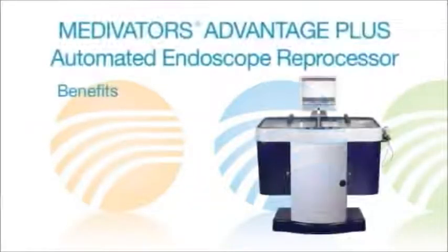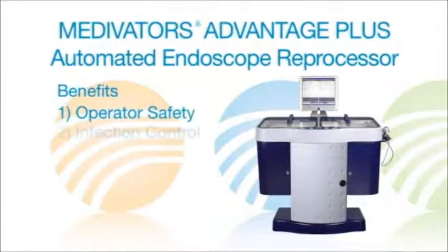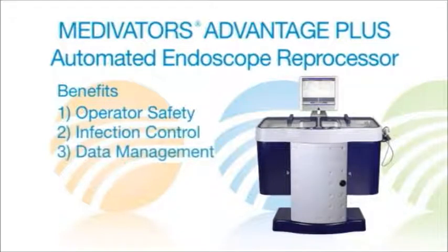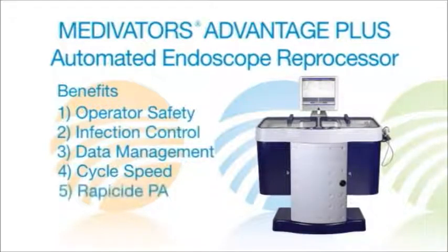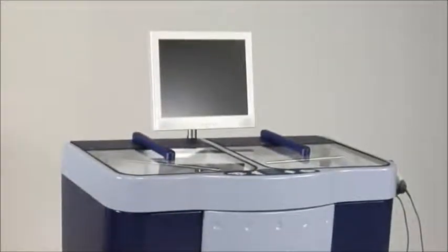The Advantage Plus was designed to meet customer needs with five major benefits: operator safety, infection control, data management, cycle speed, and the use of an environmentally friendly high-level disinfectant called Rapicide PA. These units provide a validated method for reprocessing endoscopes in as fast as 22 minutes after manual cleaning. Medivators is committed to the highest quality of patient care. After the endoscope is cleaned in accordance with the instructions provided in the scope instruction manual, this reprocessor will help to ensure operator and patient safety.